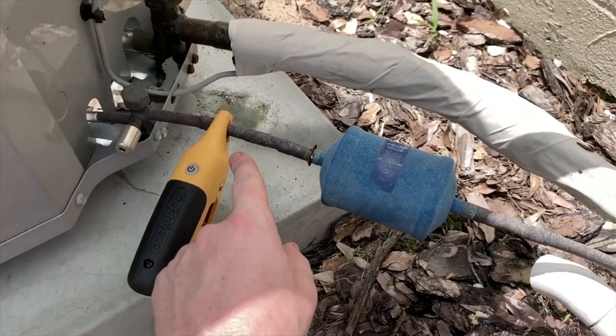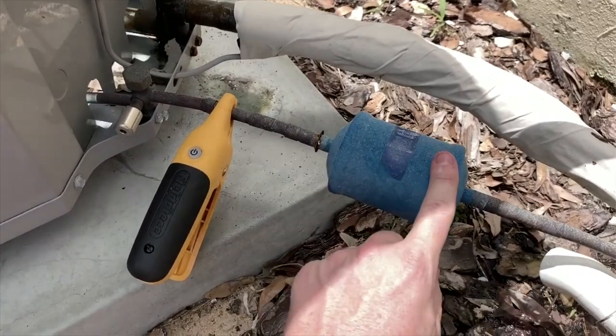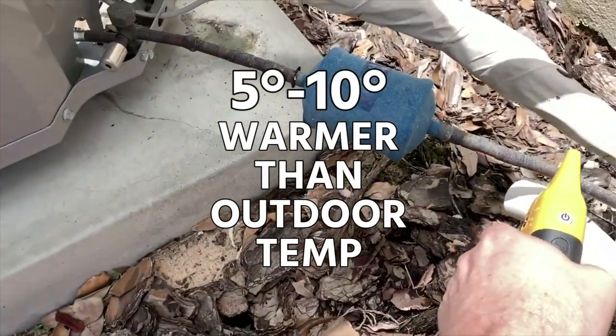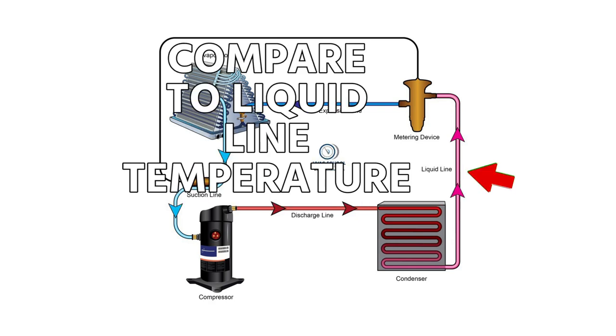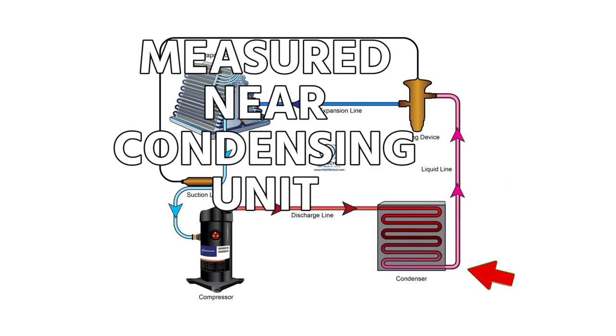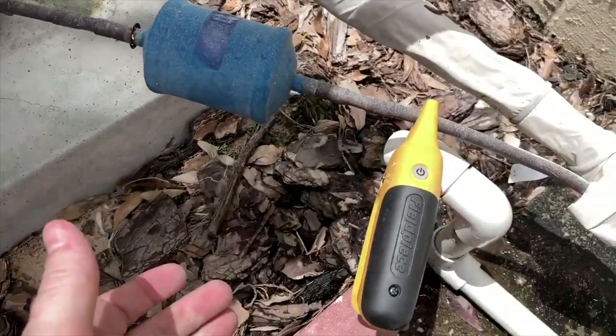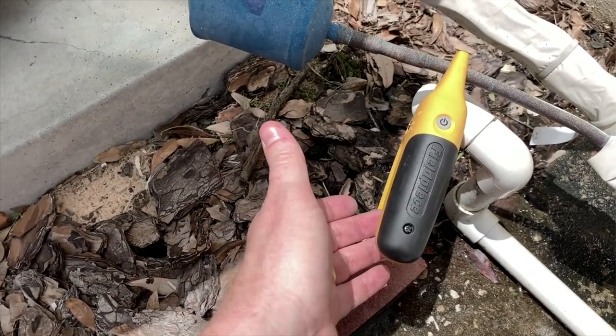Liquid line temperature — we did a separate video on how to locate your liquid line temperature. In general, your liquid line temperature is going to be about five to ten degrees warmer than your outdoor temperature on normal modern equipment. That's going to be typical, but you're going to want to know something about your equipment before you come up with that. That's what we call approach — if you take your outdoor temperature and compare it to your liquid line temperature measured near the condensing unit, you should see that liquid line temperature is five to ten degrees warmer than your outdoor temperature.